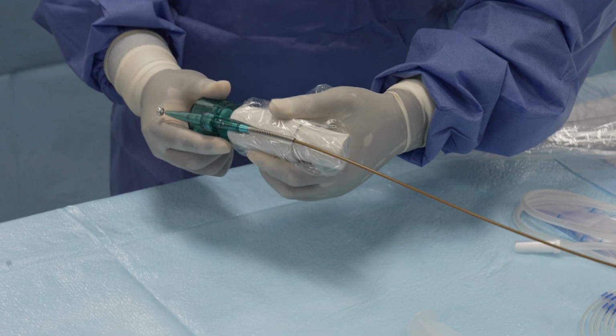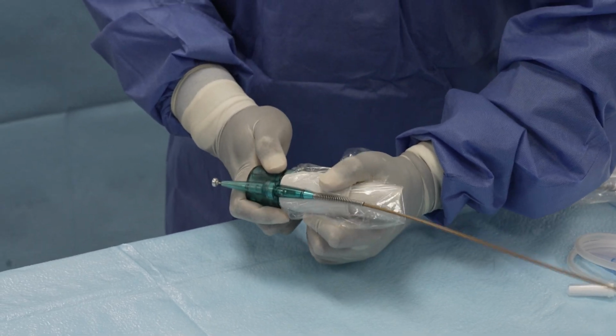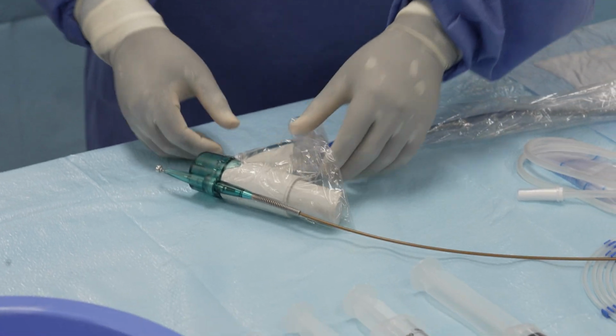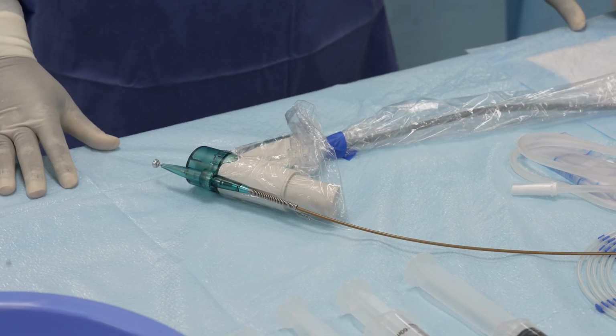Step 5. Press catheter onto motor. Press the catheter onto the motor. Lateral plates must click into the corresponding structure of the motor housing. Make sure that the catheter locks firmly into position.